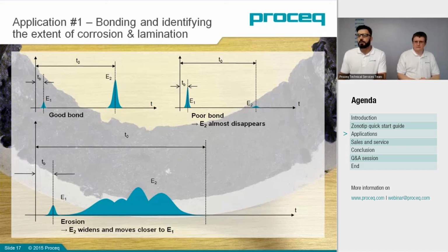On that note, before I go to the demo table and start zeroing my device and doing a quick calibration for steel, and show you the corrosion example that I have here, I'm just going to quickly talk about bonding and how easy it is to identify with Zonotip. In the first case, when we have a good type of bonding, it's common to see a very small echo and a larger echo at the back, and that means most of the ultrasound is traveling all the way through. When you're dealing with a poor type of bonding, it's common to see a larger echo before the back wall echo. That means the majority of the sound is not traveling to the back wall, and that indicates the bonding is not necessarily great. When we're dealing with erosion, it's common to see an echo and then a scatter of multiple echoes, and that indicates there's possibly something wrong in that area and it requires more inspection.